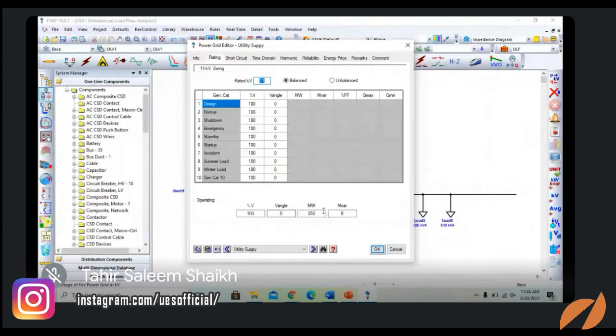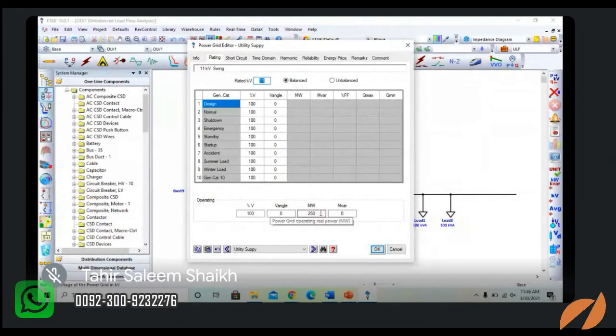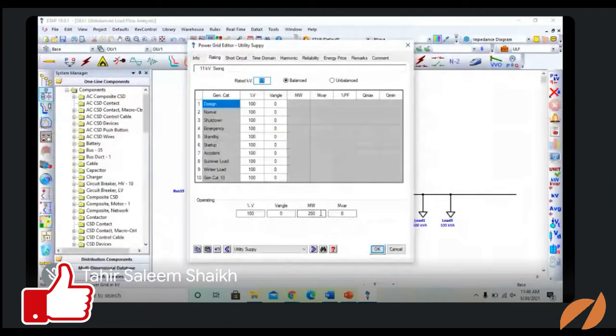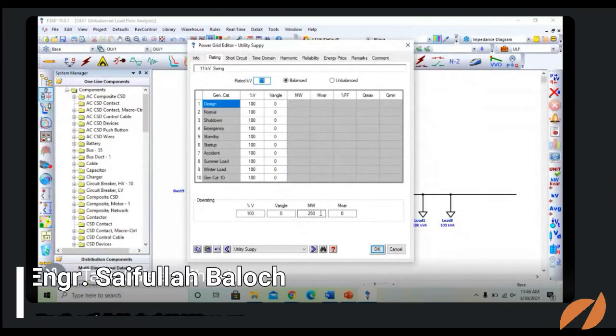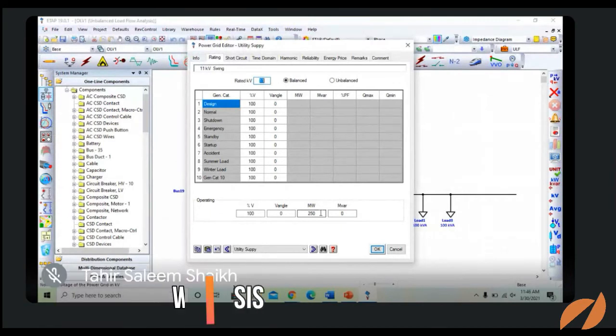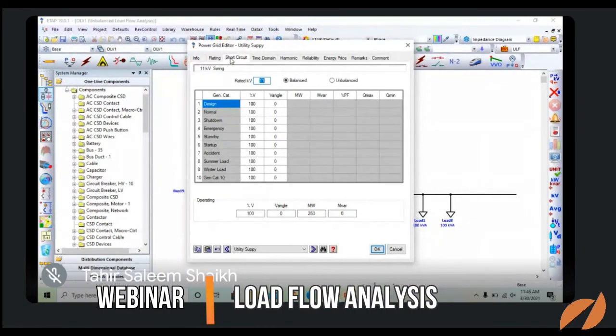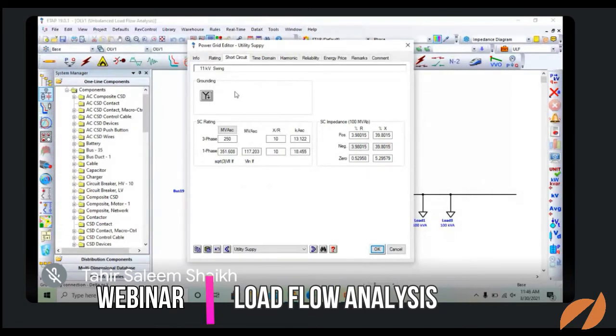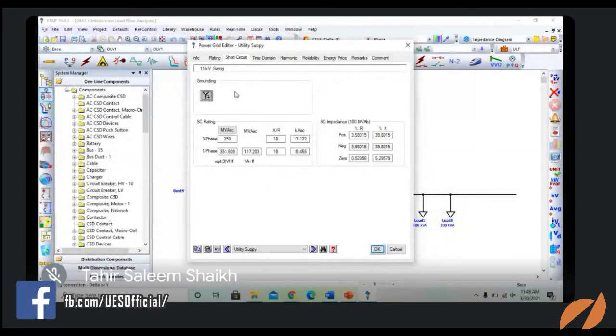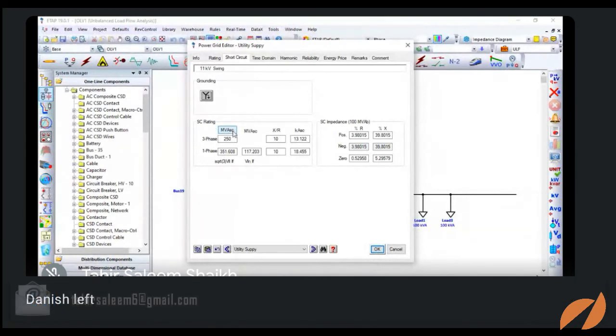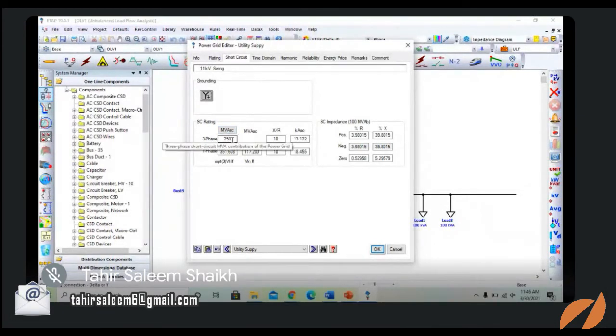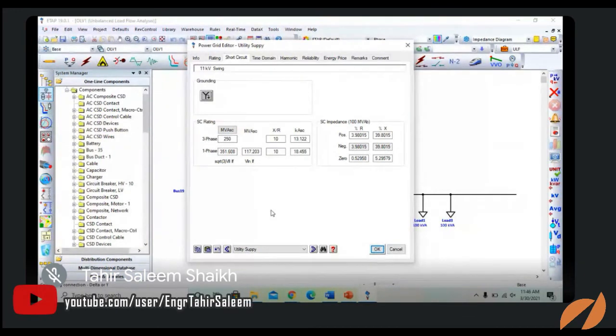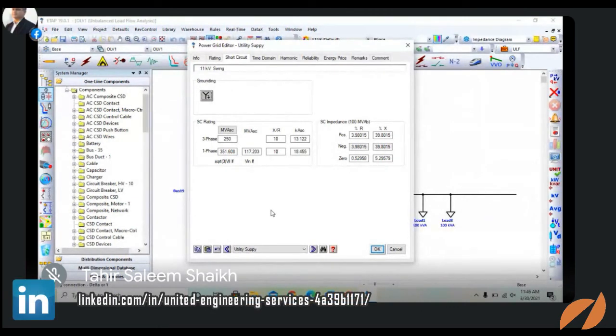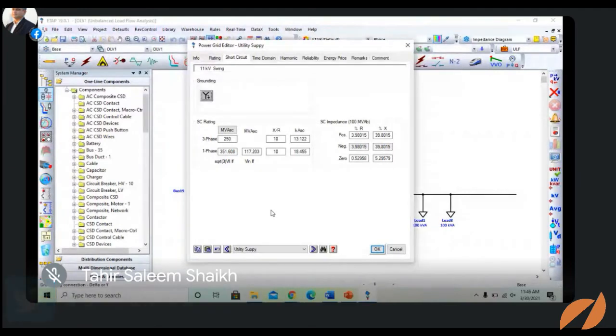Now what is the MVA and megawatt rating? That is the power grid's real-time operating rating. You can change it by yourself, but for this small commercial or small industrial power system, 250 megawatt is enough. You can also select the MVA rating, but I'm giving it 250. Now the short circuit rating, that is the MVA short circuit. For the 3 phase I have selected 250, and if you have any big utility company, you can also select 500 MVA.